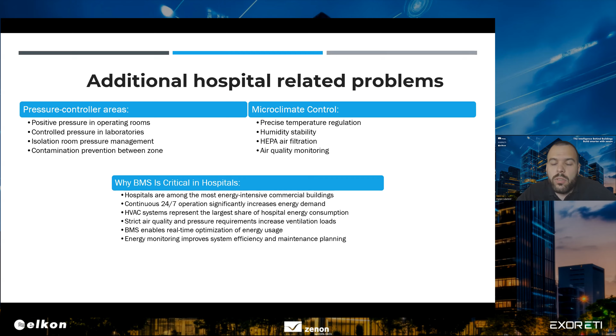So what were our tasks in this project specifically? Obviously, heating substation control and monitoring, domestic hot water, monitoring and controlling of 9 air handling units, maintaining positive pressure inside operating rooms, surgical blocks, and so on. Negative pressure in labs, strict staircase and elevator shaft pressurization, fire damper monitoring, humidity control, strict temperature regulation in critical areas such as ORs, NICUs, and ICUs, integration of all FanCoils, electrical generators, UPSs, lighting control of corridors and external building lighting.